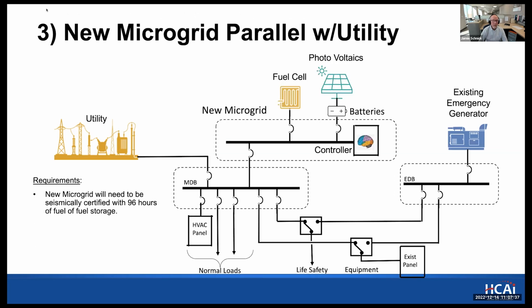And finally, the microgrid solution. With this solution, you would be able to install a new microgrid, which parallels the normal system and backs up the entire facility. The microgrid itself would need to be seismically certified and provide for the 96 hours of fuel. In this case, the entire site would be backed up, and you would not need to go back and adjust the current fuel requirements for the existing generator.